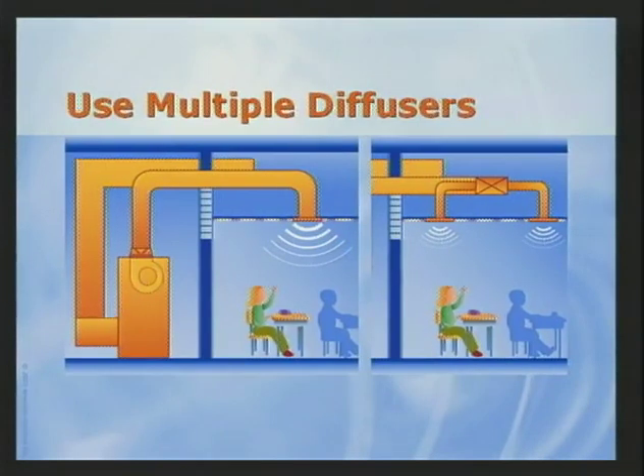A diffuser is the entry point to the room for duct-borne sound, but diffusers also generate sound. The sound power data provided by the diffuser manufacturer must be added to the duct-borne sound. Select diffusers with care to avoid increasing the overall sound level in the space and to help create a balanced spectrum. I've mentioned several changes that can be made to improve near-room units. Here's a specific example using a water source heat pump.